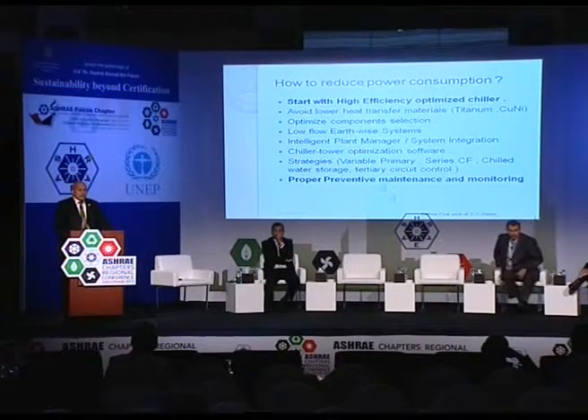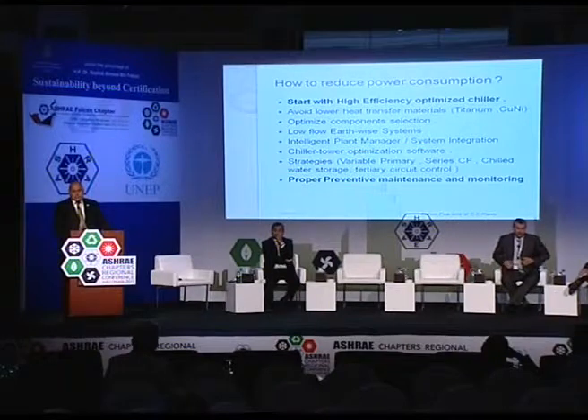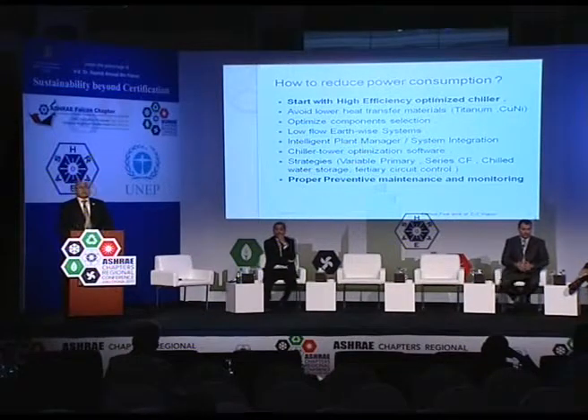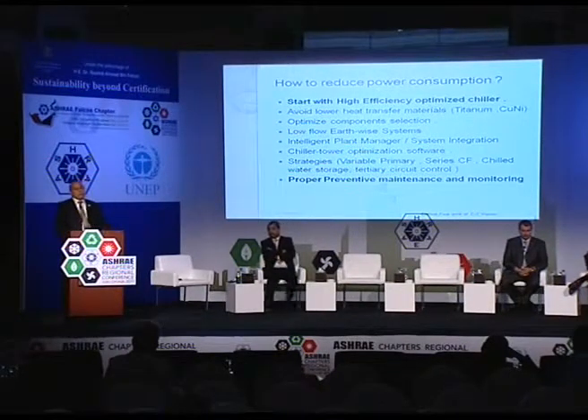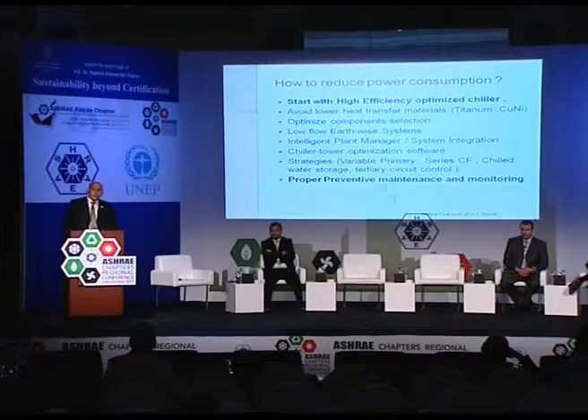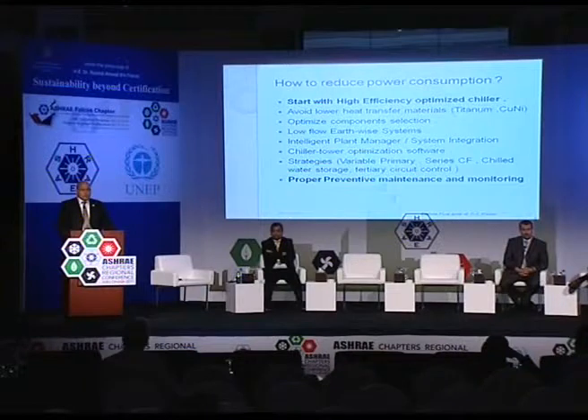Try to avoid titanium or copper nickel tube. We all know that copper nickel and titanium will last longer, but over the lifetime of a chiller, you'd be putting in 7 or 8% more kilowatts because they have less heat exchange capability than copper. Please try to avoid them. You need to optimize your components, of course.